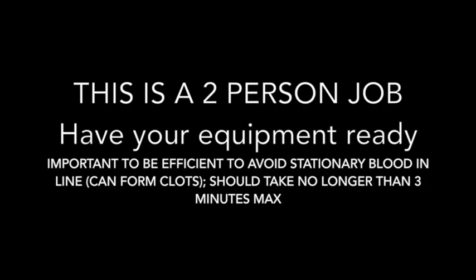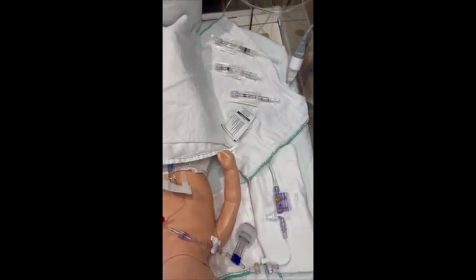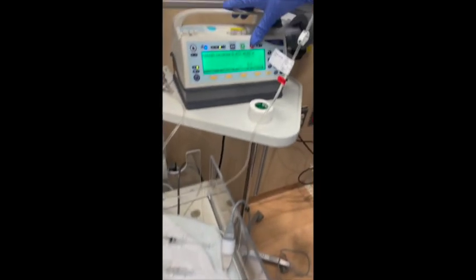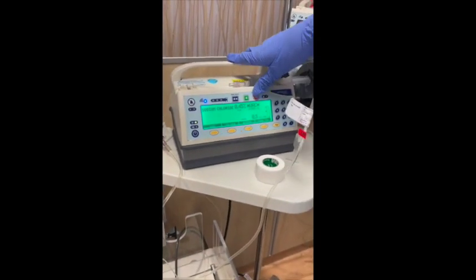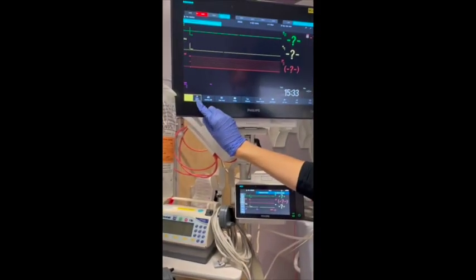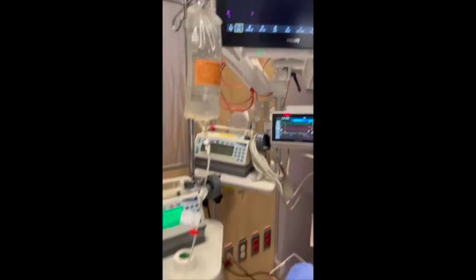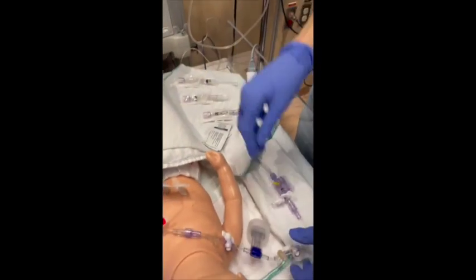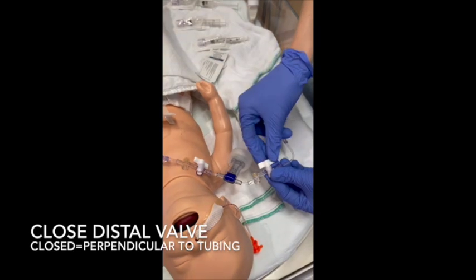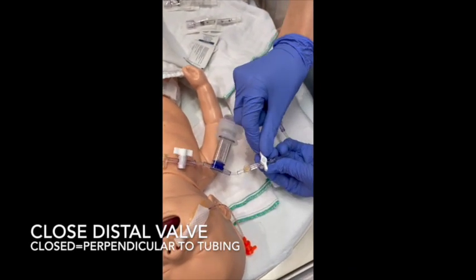It is important to perform arterial blood draws efficiently to avoid stationary blood in the line, which may result in clot formation. Stationary blood should remain in the VAMP Junior for no longer than 3 minutes maximum. Silence ECG monitor alarms for a line with monitored blood pressure. Pause the infusion on the syringe pump. Close the distal valve by turning the handle perpendicular to the tubing.